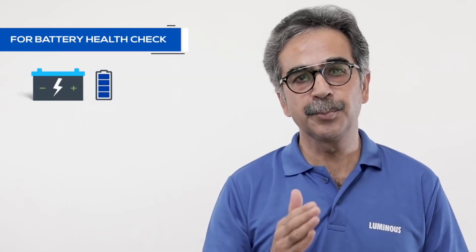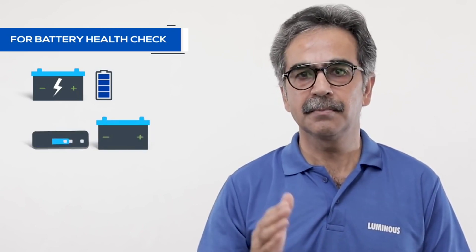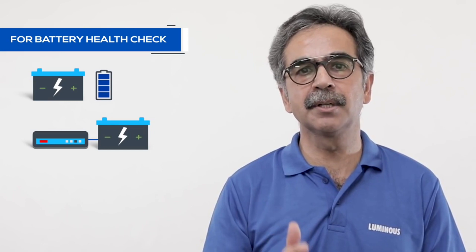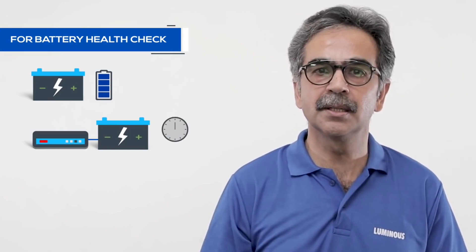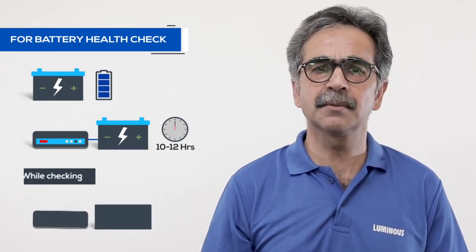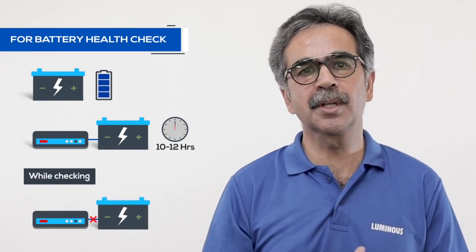For the battery health check, the battery needs to be fully charged. Before you check the battery, ensure that the battery is connected to a good inverter or charger for 10-12 hours. When you check the battery, disconnect the battery from the inverter and ensure that there is no load.